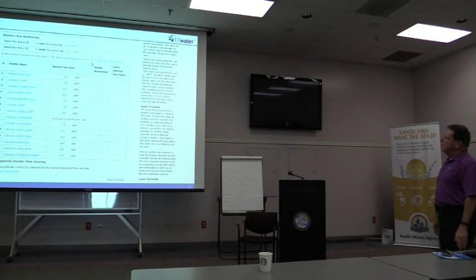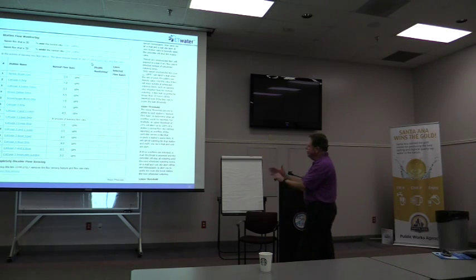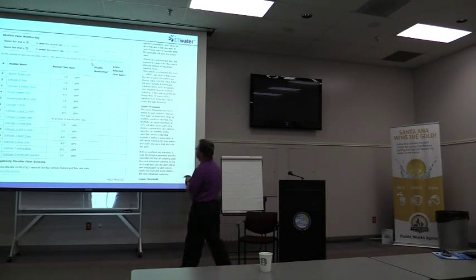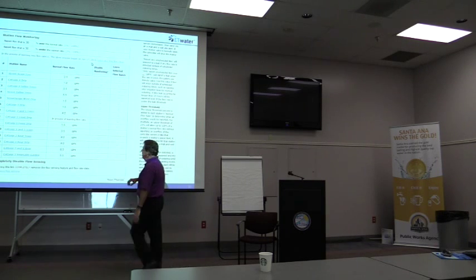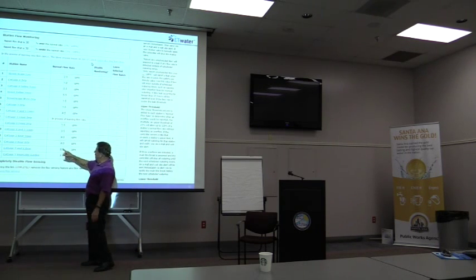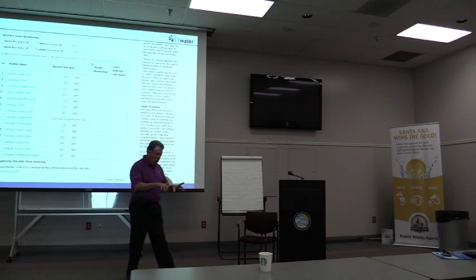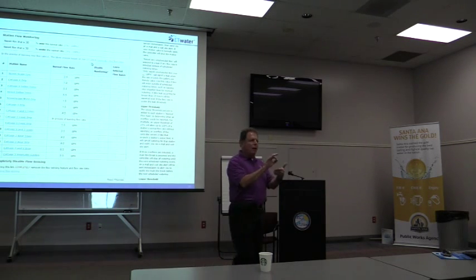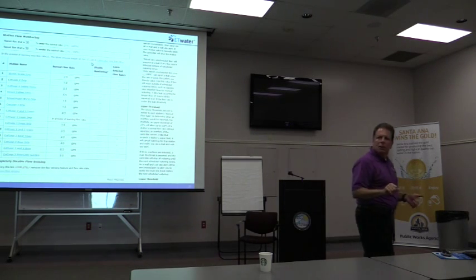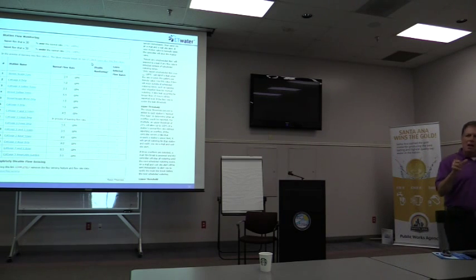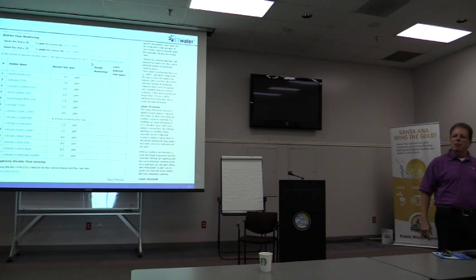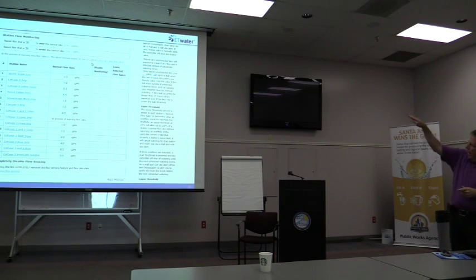This shows a controller for, I think, a project in Vegas. You'll notice these station flows here, 5.5, 6.5, and so on. These flows are automatically learned, no one went into the system and filled out a database. The system was told what size and type of flow sensor, so we know what these pulse rates represent as far as flow, and we automatically learn the flows. What you notice is station number 8 hasn't learned flow.